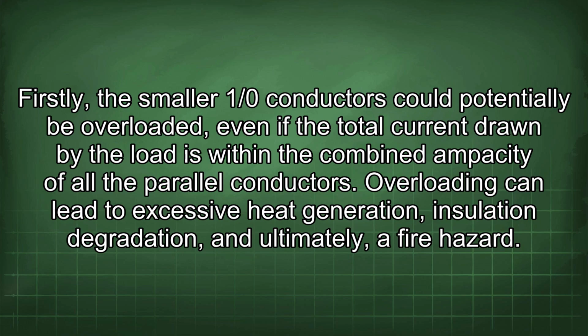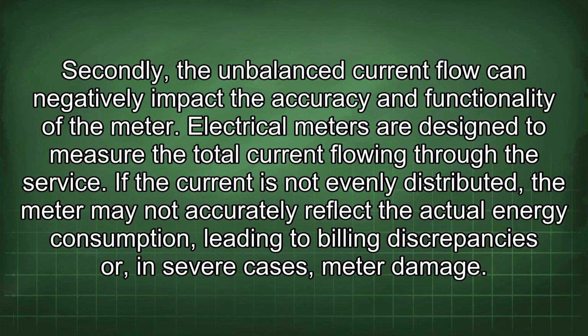Overloading can lead to excessive heat generation, insulation degradation, and ultimately a fire hazard. Secondly, the unbalanced current flow can negatively impact the accuracy and functionality of the meter. Electrical meters are designed to measure the total current flowing through the service. If the current is not evenly distributed, the meter may not accurately reflect the actual energy consumption, leading to billing discrepancies or, in severe cases, meter damage.